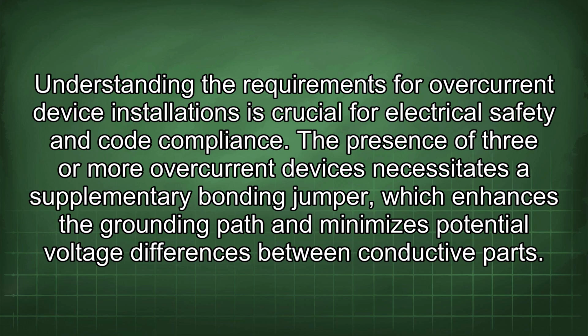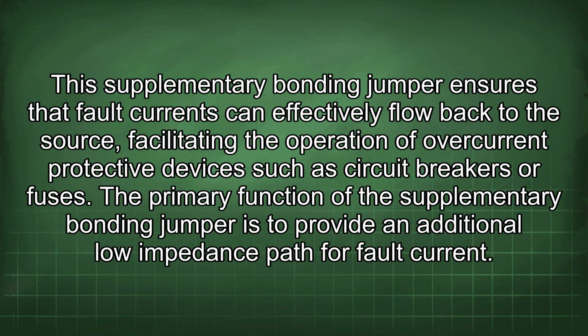The presence of 3 or more overcurrent devices necessitates a supplementary bonding jumper, which enhances the grounding path and minimizes potential voltage differences between conductive parts. This supplementary bonding jumper ensures that fault currents can effectively flow back to the source, facilitating the operation of overcurrent protective devices such as circuit breakers or fuses.